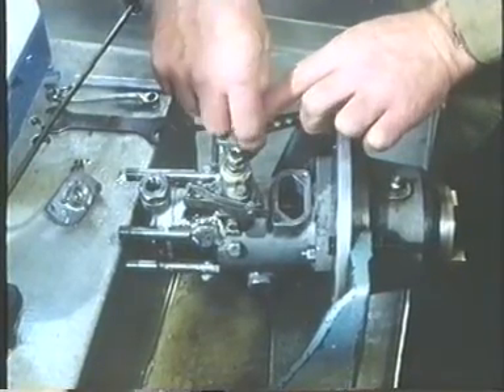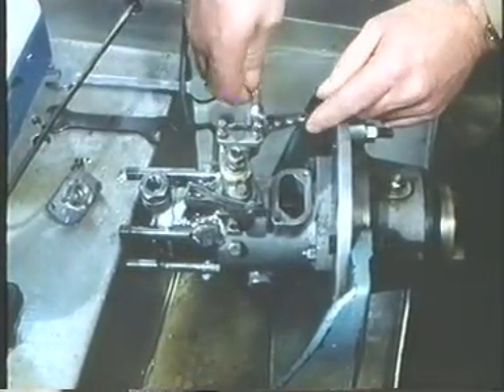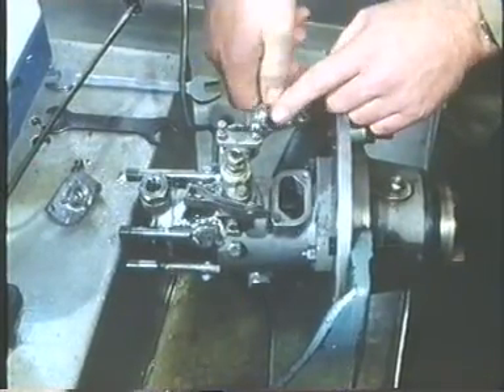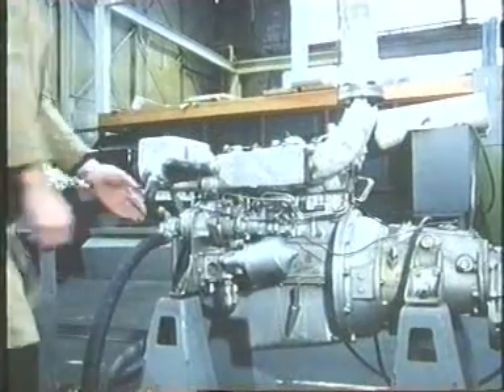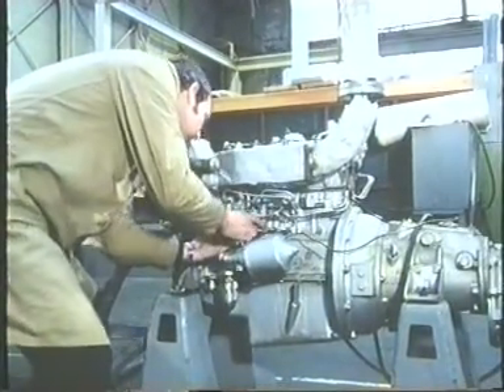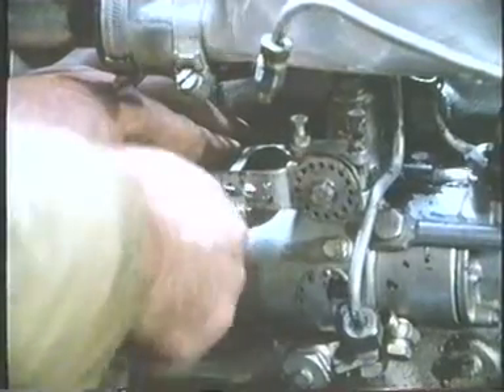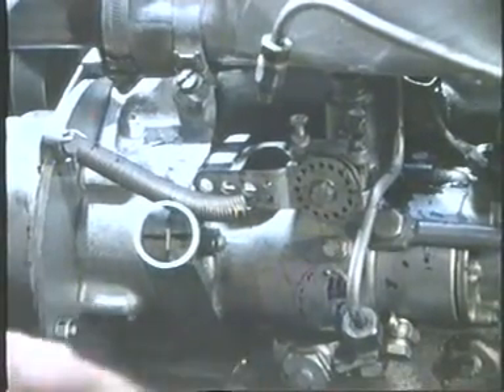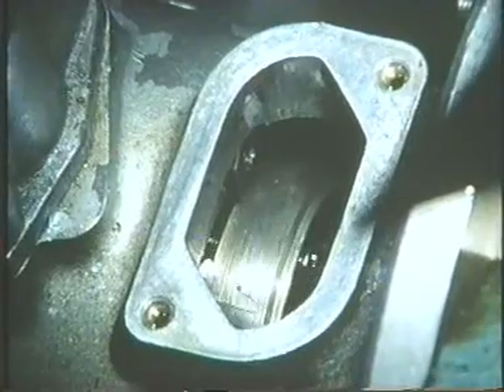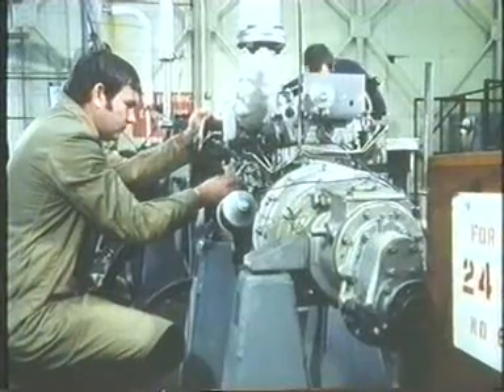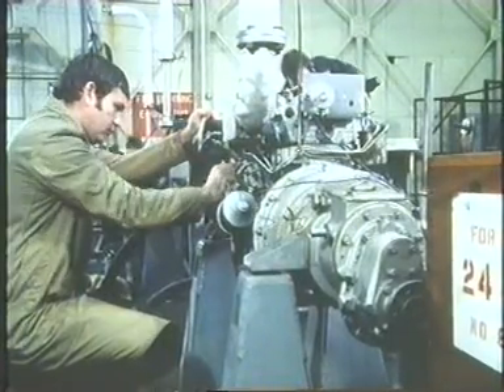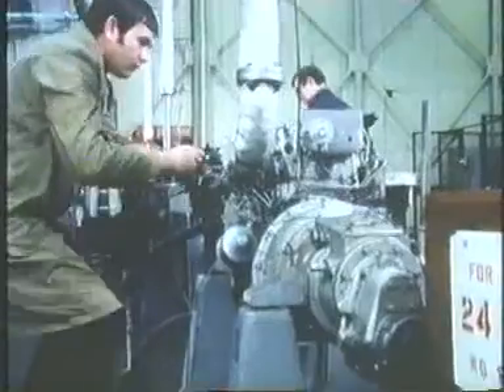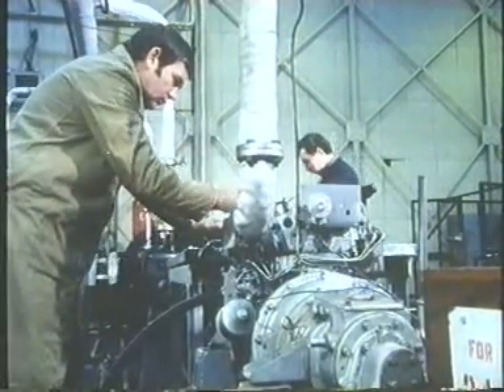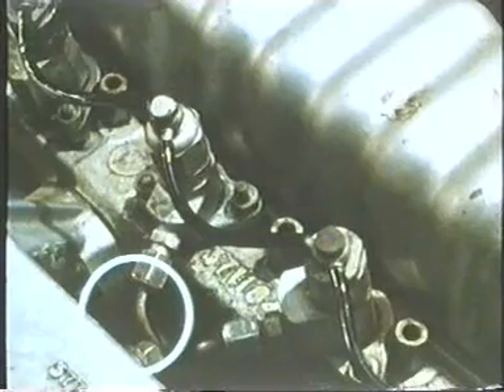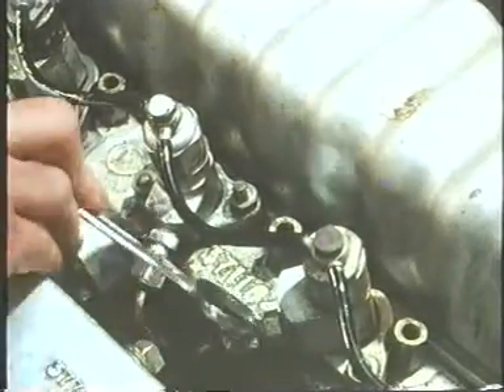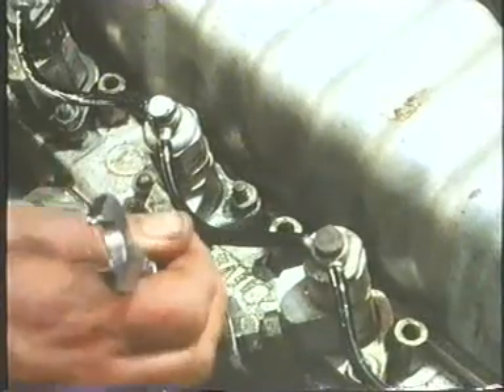Timing the pump to the engine is relatively straightforward, but the exact procedure must always be followed according to the type of engine. In all cases, timing marks scribed on the edge of the pump mounting flange must be accurately aligned with the timing marks on the engine. Whilst an incorrectly timed pump cannot damage the engine, it could result in failure to start. This could have serious consequences if the engine is required to fulfill its task in an emergency. Here, the pump is being primed ready for the first start-up after refitting.